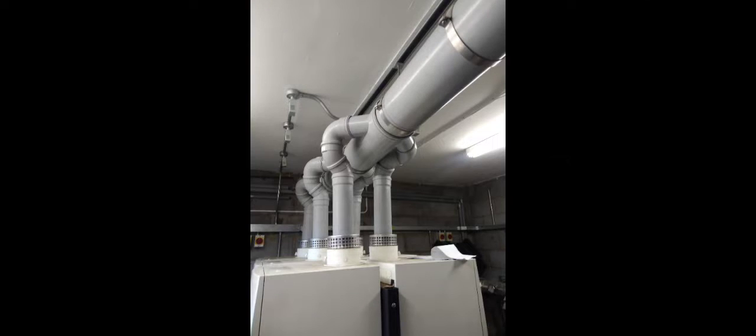In this job, I believe I was just changing a standard pressure switch on a Vaillant boiler. I'm sure you've done many of these. Sometimes you can just clean up these pressure switches, but they're cheap and it's best to often just replace them. Now at this particular site, I think what happened was there was a problem with the flues. I think there were far too many bends on this flue and it needed to be taken out and redone again. So this is the picture of it beforehand.